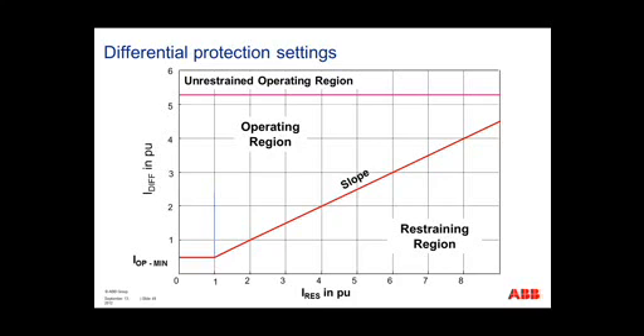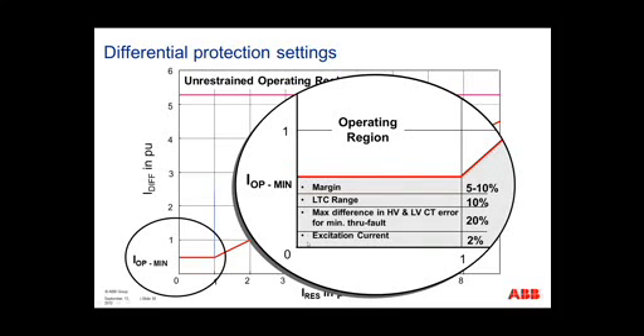When you're setting up your differential, you'll have this picture showing two regions, a flat region and a slope region. The x-axis represents current in the restraint coil, and the y-axis represents the differential current seen by the relay. In ideal circumstances, we would of course want to set this at 0, but we don't have ideal circumstances where our pickups cannot be set at 0. Anything other than 0 would trip the transformer. We have to account for certain errors. That's what raises our minimum operation current.